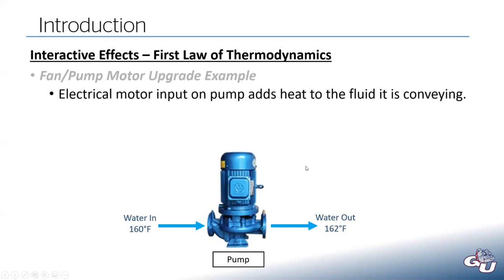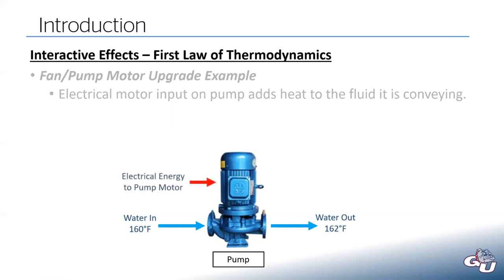Well, that electrical motor input on the pump adds heat to whatever fluid it's conveying through that pipe. So we're going to put in some electrical energy to that pump motor. You're going to get some heat off of that thing just from the inefficiency of the motor. And that's just going to go into whatever room this pump is physically sitting in. And then the rest of it is going to be transmitted into the water itself as power and eventually heat. Eventually that power will become heat.